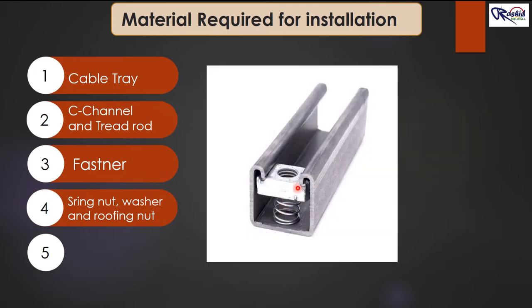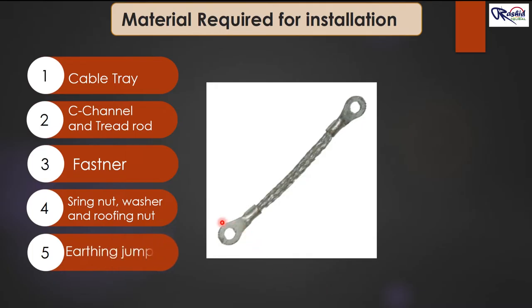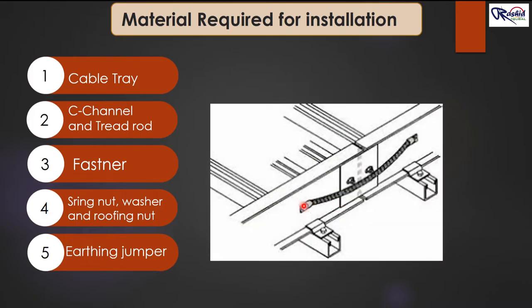Fourth, spring nut, washer and roofing bolt. Here you can see the spring nut, which is fixed inside the C-channel, then tightened at the other end of the thread rod. Fifth, earthing jumper — this earthing jumper is used to connect at the junction of two cable trays to provide the route of earthing current towards the main earth bus bar.